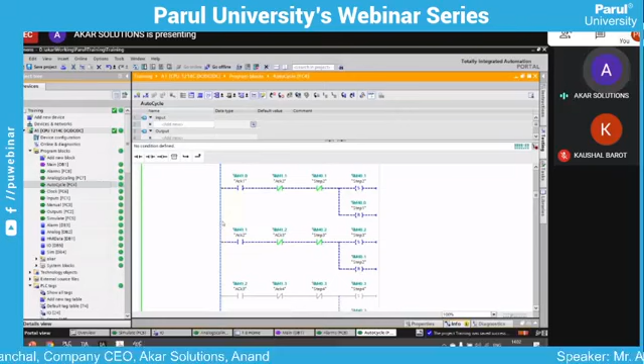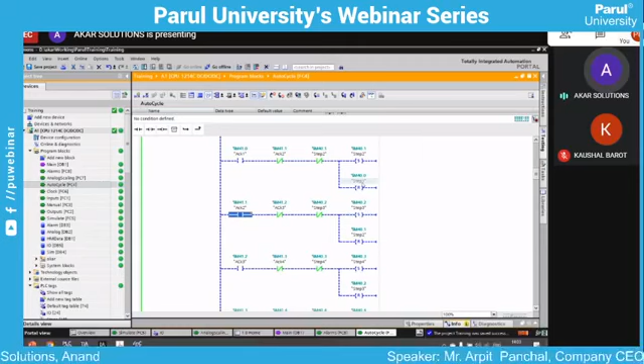And then this is just a simple step cycle, meaning it is going once, proceeding one by one. When you start the signal, it will go to step one, and when the first step is completed, it will go to step two. Then after the third step, the fourth step, this is how the logic is flowing. And this is how we are checking whether the first step is completed. When step one is running, we are checking whether the valve is open or not. When the first step is running and we receive the valve open feedback, then the first step is completed, and it will go to the next step. In the next step, we are opening the second valve. And when the second valve is open, we are starting the pump. And when the pump and two valves are running, we are waiting for the transfer to complete.